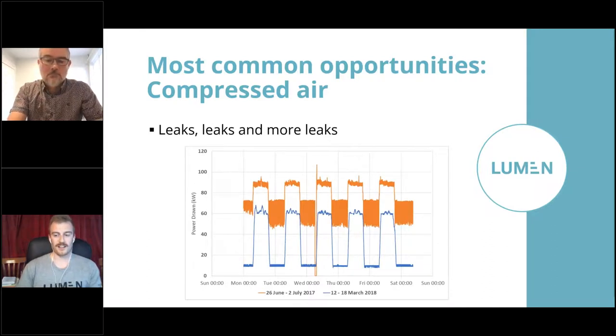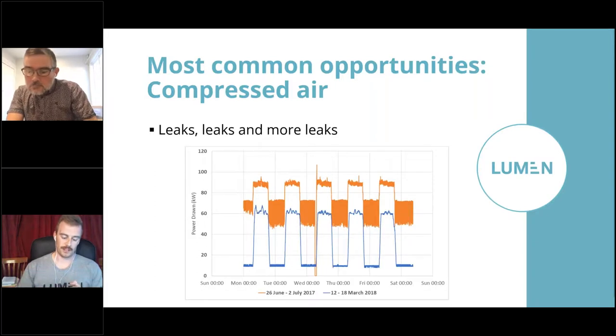The second option is to do an ultrasonic leak detection survey, and that's really one of the best ways to do it. You can commission a contractor, or you can get an ultrasonic leak detector yourself and do it yourself. But most likely, you'll commission a contractor to go around the system, basically finding where the leaks are. Make sure you actually fix the leaks. The contractor will tag those leaks when they find them and give you a report telling you what it's worth.